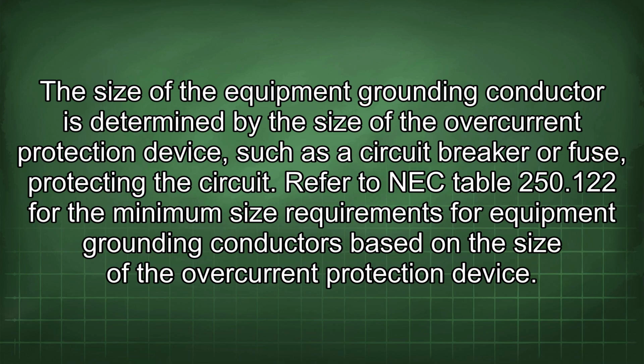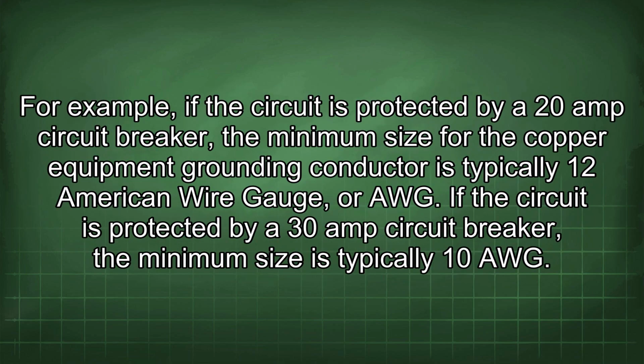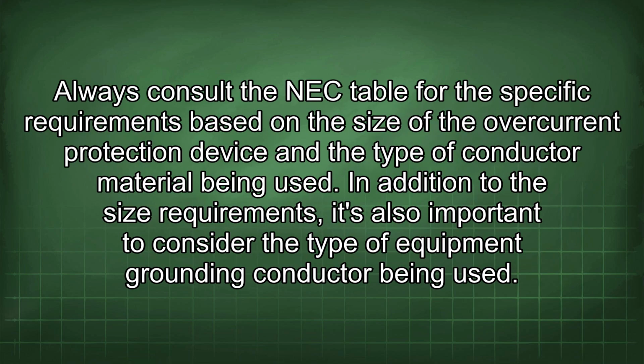Refer to NEC Table 250.122 for the minimum size requirements for equipment grounding conductors based on the size of the overcurrent protection device. For example, if the circuit is protected by a 20 amp circuit breaker, the minimum size for the copper equipment grounding conductor is typically 12 American wire gauge, or if the circuit is protected by a 30 amp circuit breaker, the minimum size is typically 10 AWG. Always consult the NEC table for the specific requirements based on the size of the overcurrent protection device and the type of conductor material being used.